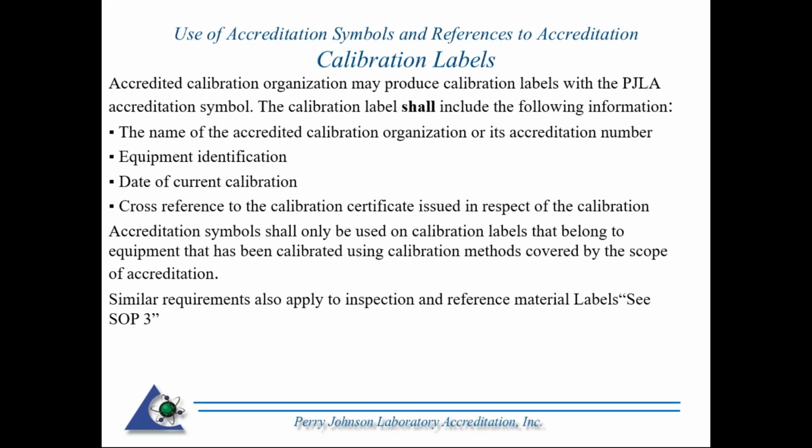So in other words, one of the requirements is you have to have a unique identifier. I'm talking about requirements for reporting the results now, section 7A. So perhaps you have a certificate number. So this is stating if you're using the logo, these things have to be mentioned, and you also have to mention that certificate number that's unique to that particular calibration.